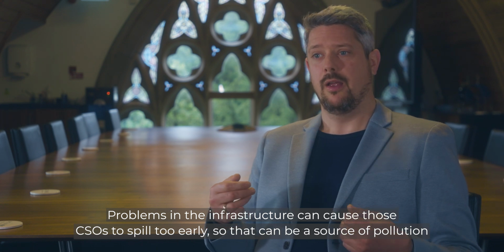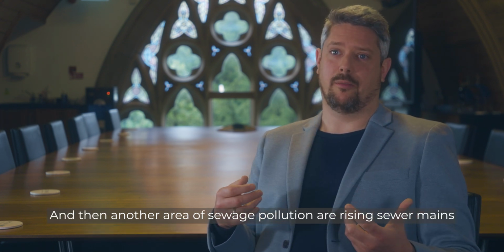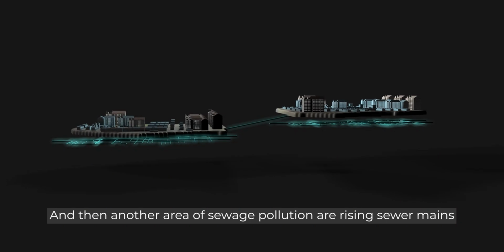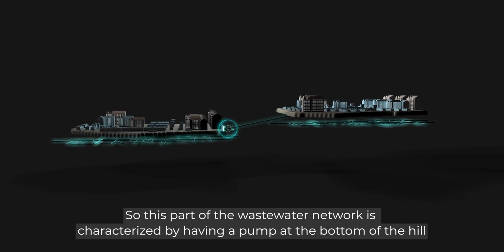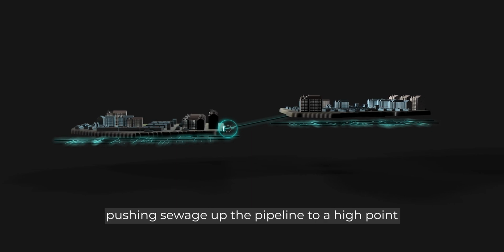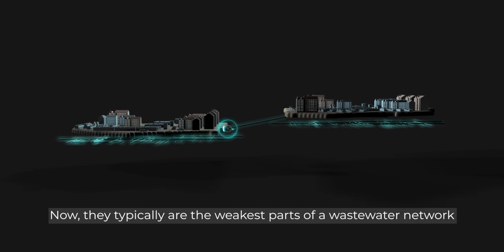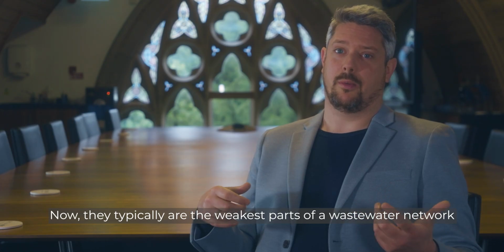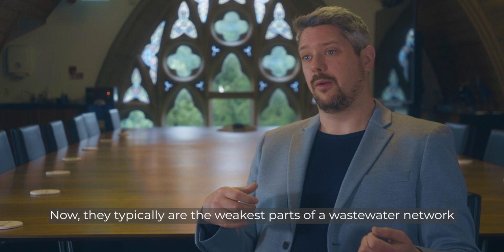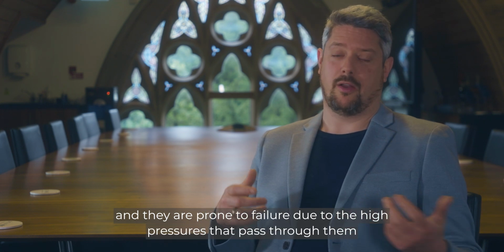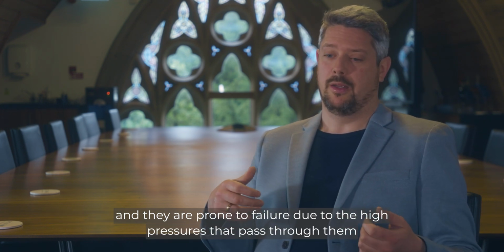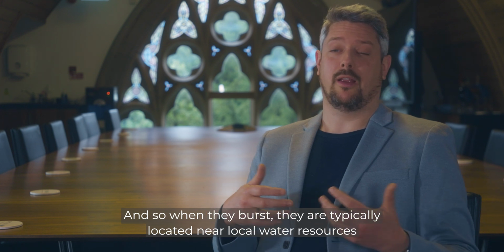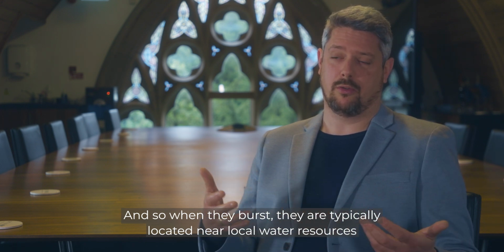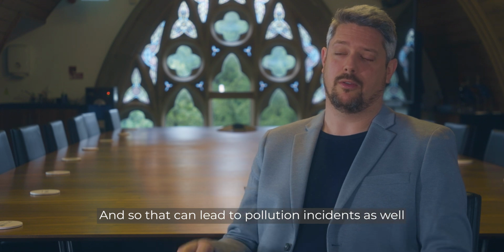And then another area of sewage pollution are rising sewer mains. So this is part of the wastewater network. It's characterised by having a pump at the bottom of a hill, pushing sewage up the pipeline to a high point. Now, they typically are the weakest part of a wastewater network, and they are prone to failure due to the higher pressures that pass through them. And so when they burst, they are typically located near local water resources, and so that can lead to pollution incidents as well.